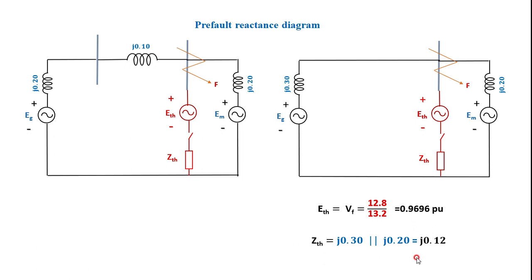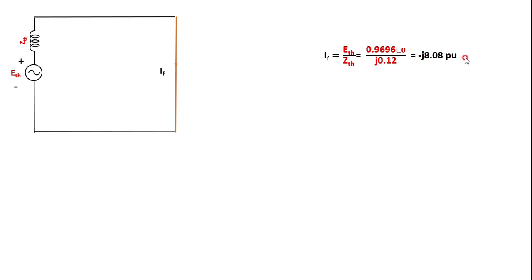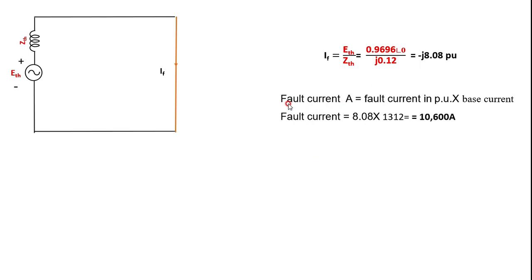The simplified Thevenin equivalent circuit has the Thevenin voltage source ETH = 0.9696∠0° and the Thevenin reactance j0.12 in series, from which the fault current is calculated. The fault current equals ETH divided by ZTH: 0.9696∠0° divided by j0.12, giving a fault current of -j8.08 per unit. Multiplying by the base current of 1312 amperes gives a total actual fault current of 10,600 amperes.